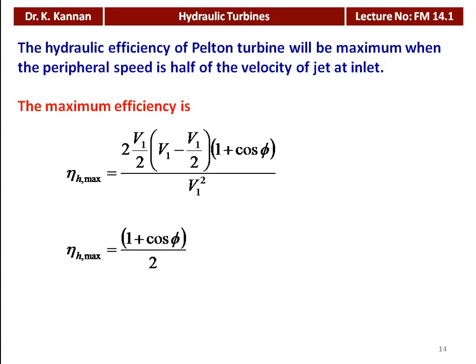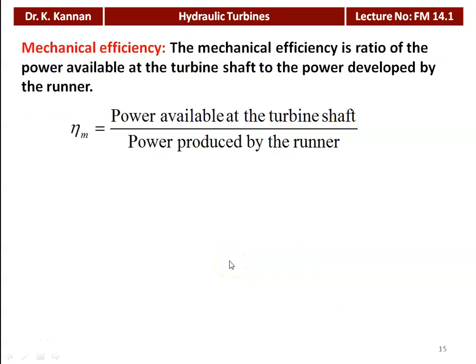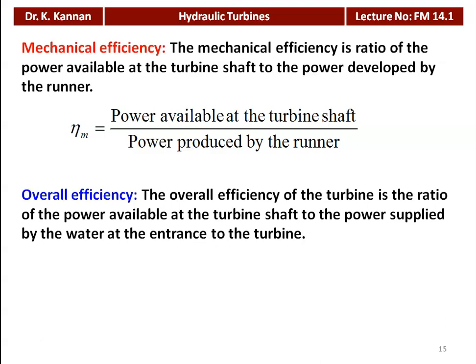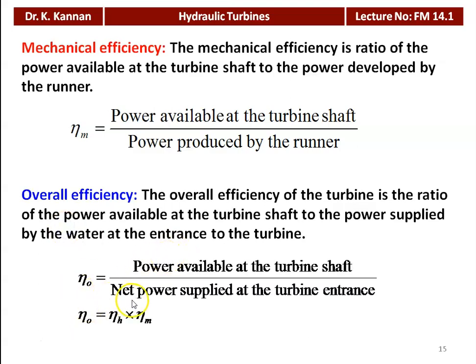The mechanical efficiency of the Pelton turbine is the ratio of power available at the turbine shaft to the power developed by the runner — it accounts for frictional losses in the runner, shaft, and end bearings. The overall efficiency = power available at turbine shaft / net power supplied to the turbine at entrance = hydraulic efficiency × mechanical efficiency.